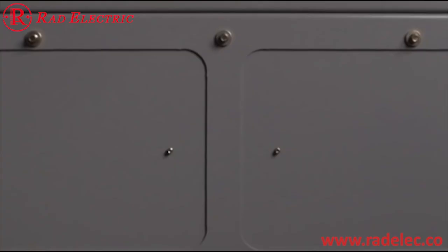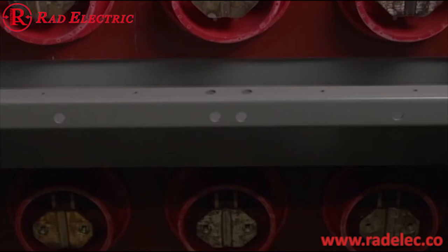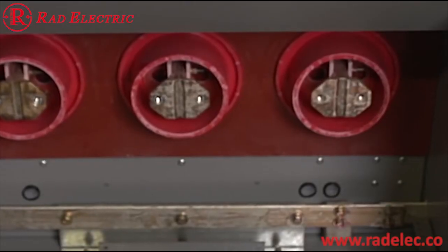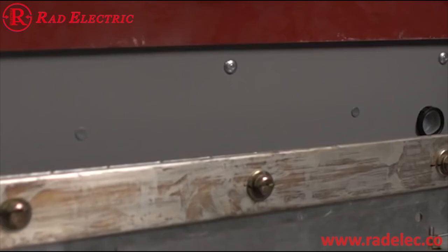This is the low voltage compartment, so this is left empty. These upper circuit breaker bushings connect to vertical bus that then connects to the main horizontal bus. And all the way at the bottom, we have the runback connections for the circuit breaker. These angled pieces are for mounting bus supports. This bracket could be used for a space heater. In addition, our partners need to add approximately 28 inches of additional depth to create a cable compartment and to finish the back of the switchgear.